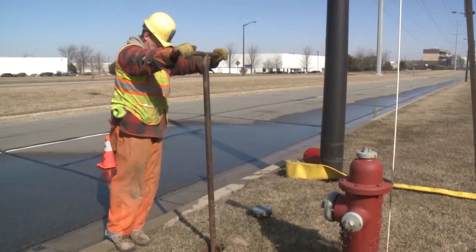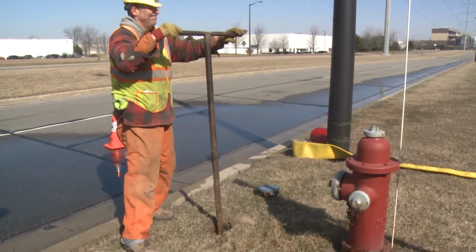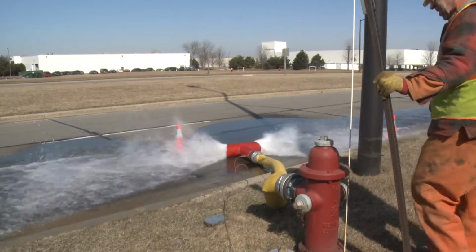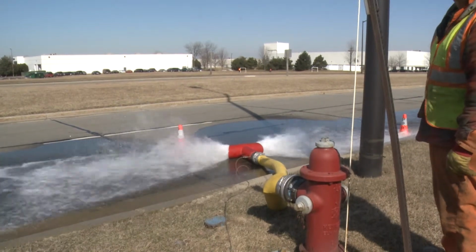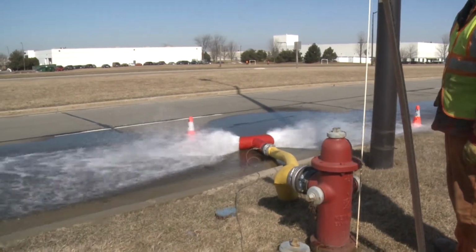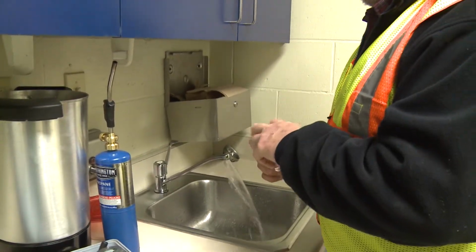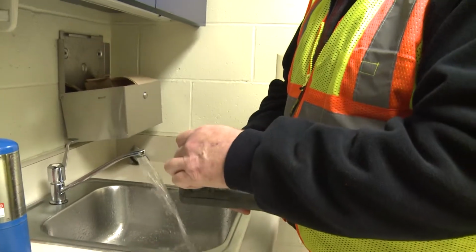Pleasant Prairie's utility also performs regular maintenance, like exercising water valves, routinely monitoring water mains, and routinely inspecting the inside of towers, reservoirs, and pumping stations. Pleasant Prairie flushes all distribution mains biannually and checks all Pleasant Prairie fire hydrants for soundness. Since the utility increased the level of ongoing maintenance, main breaks in the village water system have declined from 1 or 2 per week to about 1 per year. By paying attention to the details, staff endeavors to run the utility as efficiently as possible.